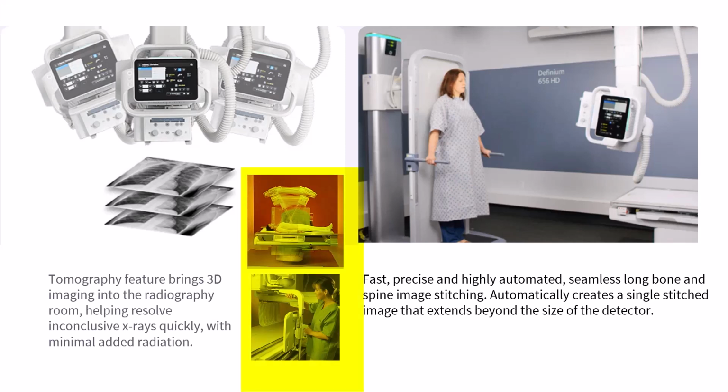The modern tomography system eliminates the old hooking up of the bucky and the overhead tube head with an awkward armature. Also, you don't have to adjust the fulcrum height for each cut. This is all done automatically for you.